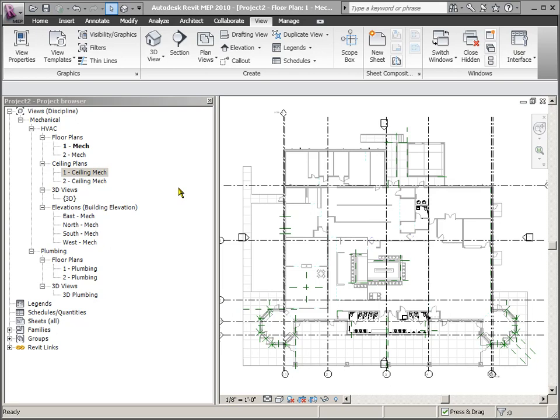a reflected ceiling plan is from the perspective of a person standing inside the room looking down at a mirror on the floor. In the mirror, the reflection shows the ceiling grid and the objects in the ceiling grid, and then your ductwork is behind that as you go up above. So your diffusers hide your ductwork above in a true reflected ceiling plan.